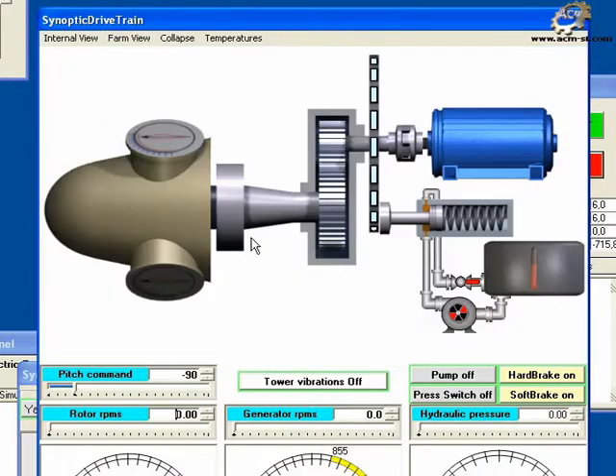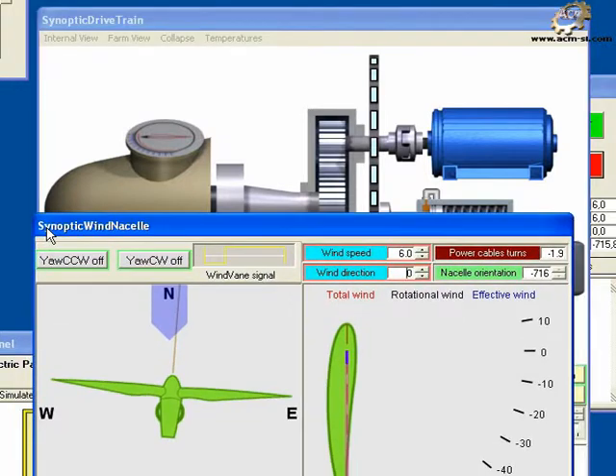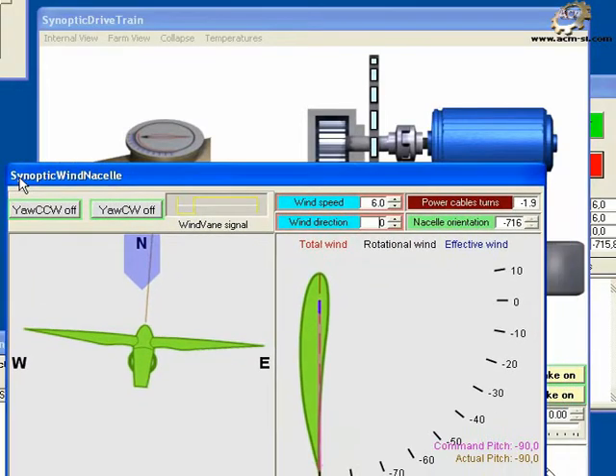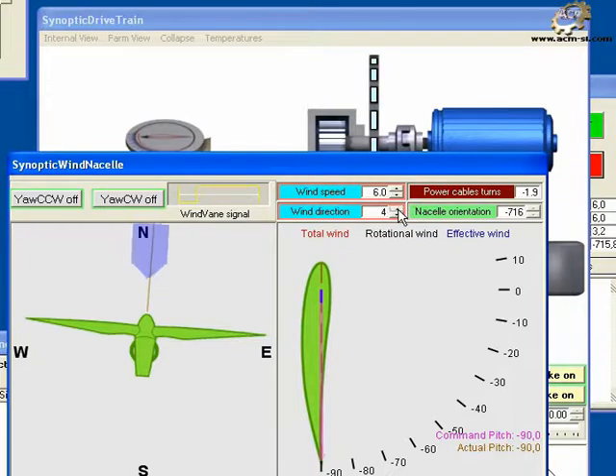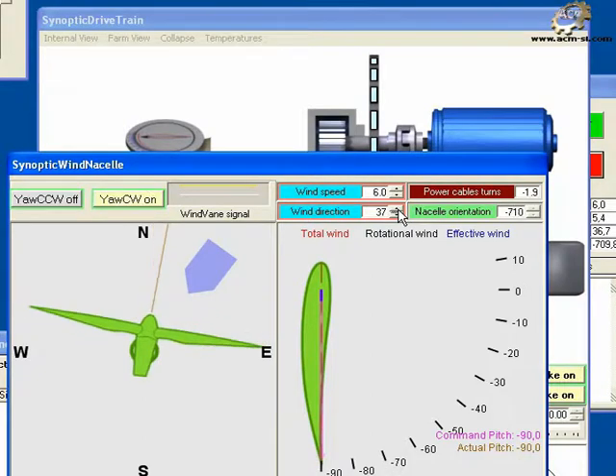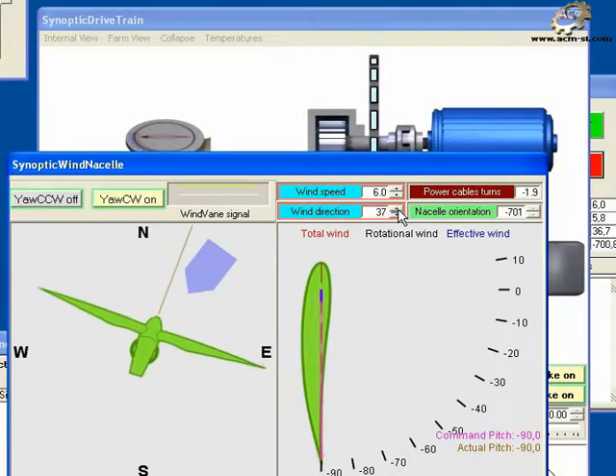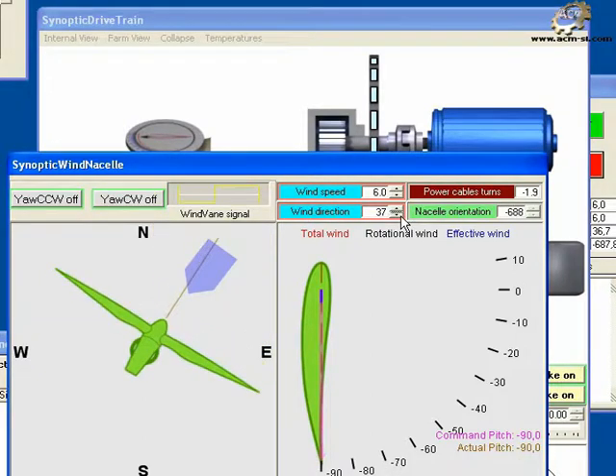Watch the nacelle orientation change in the various views of both the drive train synoptic and the wind direction. Notice that as the wind direction changes, the nacelle does not arrive at the exact value of the wind direction. This is due to the yawing system operation.